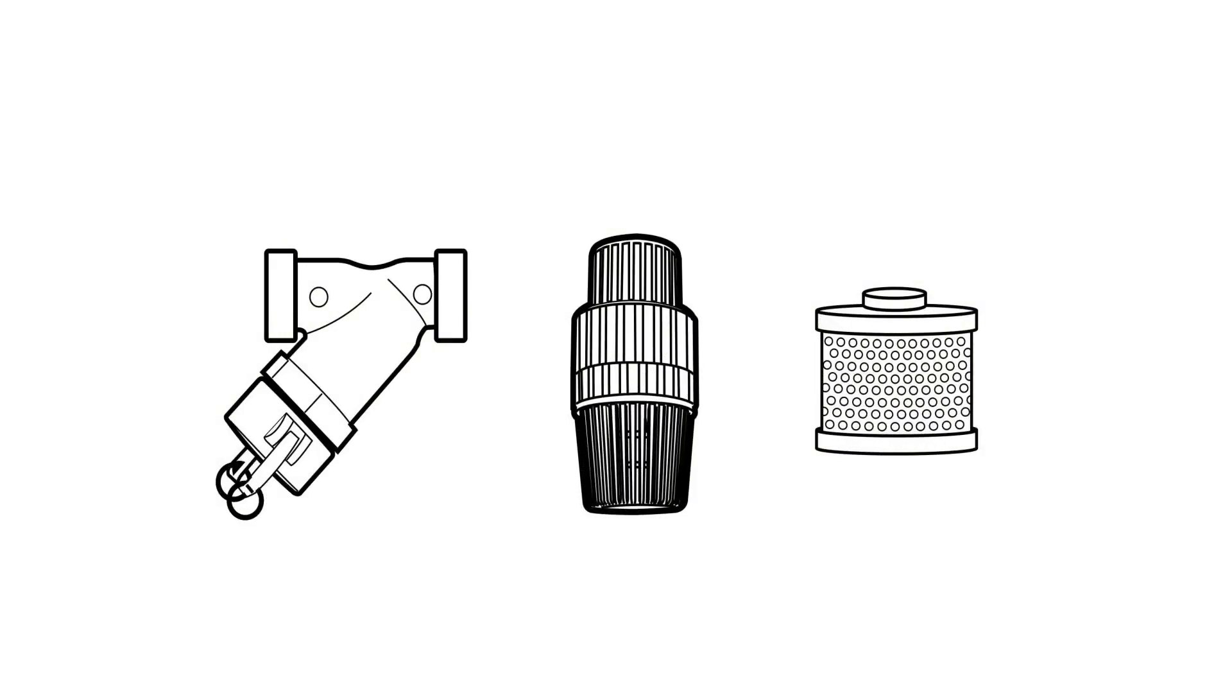Don't forget to check for debris in the foot valve that is submerged in your water source as well as the inline strainer. Debris can hold the foot valve wide open causing the suction line to drain.